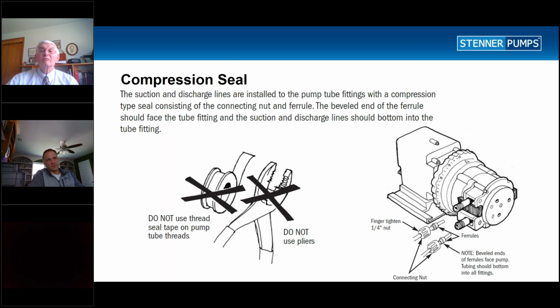Once again, we talked about not using tape, not using tools, just finger tighten. With the ferrules right here, you want to make sure that the mushroom end is facing the tube. If you put the ferrules in backwards, there's a good chance that they will leak. So you want to make sure that you always have the mushroom end facing the tube.